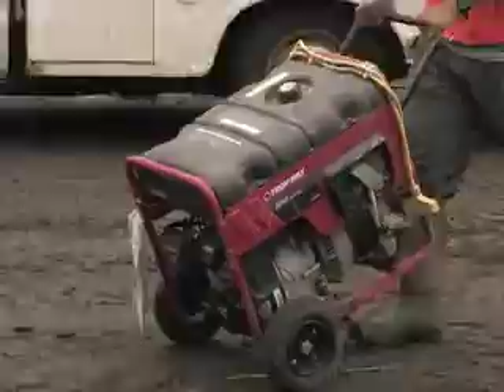Another tip for handling electrical devices is to utilize GFCIs, or ground fault circuit interrupters. These monitor the circuit to make sure what is going out is the same current that's coming back. If there is a difference in the current in the line, the GFCI will detect this difference and trip within 1/40th of a second. This device is there to save people, not equipment. Circuit breakers are in place to save equipment. GFCIs are much quicker and trip at 5 milliamps. This is a critical piece of safety equipment with tools that are not double insulated, as well as in the home.